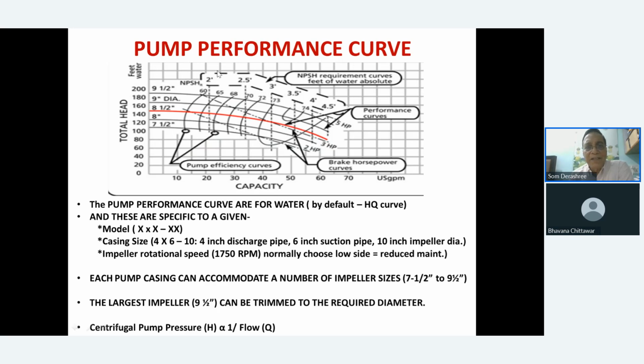Then on the top you have NPSH required. It is NPSH R. Again, we'll come to it: what is R and what is A, and what is 0.3 or 3%. These are all different nomenclatures. We'll understand it as we go further. But see, this is a typical NPSH curve. You would find that as the flow increases, NPSH also increases. So keep that in mind. And these are all known as performance curves for the pumps, basically.